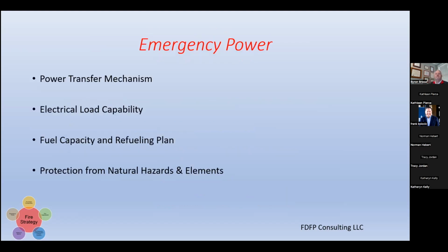Emergency power, that's key to us. We've got to maintain what you do in steady state. A steady state building is one thing. When an emergency happens, other things begin to happen, and we have to be certain that the power load is there. If you're counting on that for an appreciable period of time, you have to be very conscious of the demand on the system and the fuel capacity, and you may need a refueling plan. In some of these larger storms, from Superstorm Sandy to the hurricanes down here in the South, the best laid plans have come apart when you couldn't get a fuel truck to an emergency generator that had been running for 8 hours and probably really needed to run for 8 days. So that refueling plan is important, particularly in natural hazard situations.